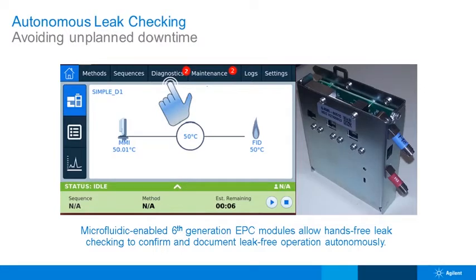Now over to another feature of the Intuvo, which is applicable now to what we're discussing primarily in this WebEx, which is the 8890 and 8860 intelligent air bath ovens: the leak checking. So we have the latest generation of EPC, which is our 6th generation EPC module. So you can see that on the right-hand side. And whenever we do any maintenance, because the GC knows exactly how it's configured, it has the ability to do automatic leak checking predominantly. This is incredibly valuable.